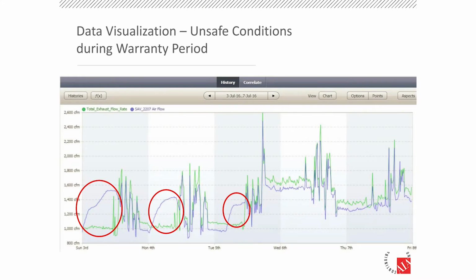I'll show you the analytics version in a second. But when this project closed out, we could verify that the labs are all operating at negative pressure. So then I'm going to fast forward 6 months ahead. The project closed out in January. Six months later, we do a 6-month review because there are seasonal changes and you want to see how the equipment is operating once it's in a heating or cooling mode that it wasn't in when you originally commissioned it. And so what we found was that all of a sudden there are some conditions here where our exhaust flow is less than our supply flow. So something in this laboratory had gone out of whack. So these are the kind of things we want to bring to the facility staff. And in this case, this building was still under warranty, which is another thing we talk about, and the benefit of monitoring is these issues that are identified are still under warranty and the responsibility of the construction team.